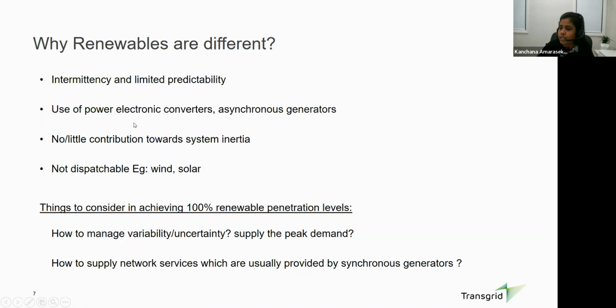The other thing is, with synchronous generators, usually they used to be large spinning machines. However, these small machines or completely power electronic based generators have no or little contribution towards system inertia. Then renewables are intermittent and have a limited predictability, and they are not dispatchable. In other words, we cannot turn them on as we want. So these different characteristics of renewables compared to conventional generators impose lots of challenges when we try to increase the renewable share in the networks.